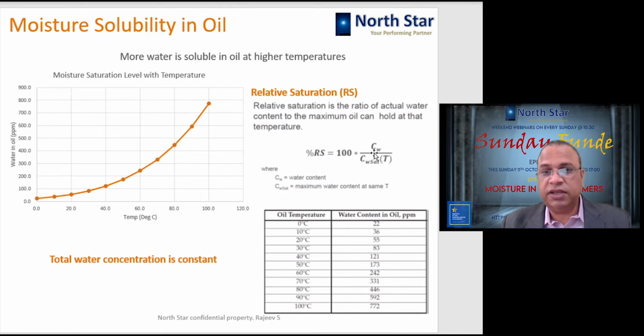So relative saturation is calculated in this way. Cw is the water content and Cw sat is the maximum water content at the same temperature. Suppose we have taken the oil sample at 40 degrees centigrade, and we find that the water content is 5 ppm, so Cw will be 5 ppm, and for 40 degrees centigrade the Cw saturation, meaning the water quantity for saturation at 40 degrees centigrade, is 121 ppm. So 5 ppm divided by 121 ppm will give you the percentage relative saturation in that particular oil sample. So this relative saturation is a very important parameter, because it tells you how much water is there in the oil and how much water you found in the sample.